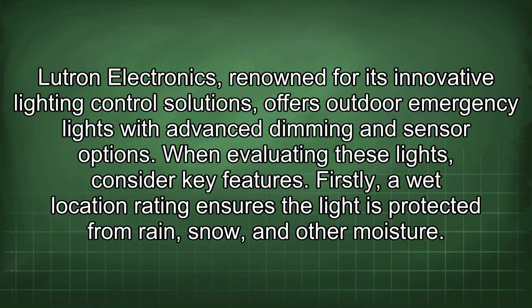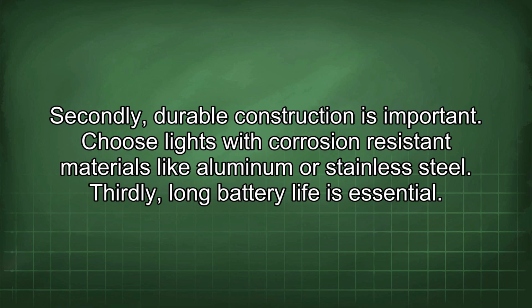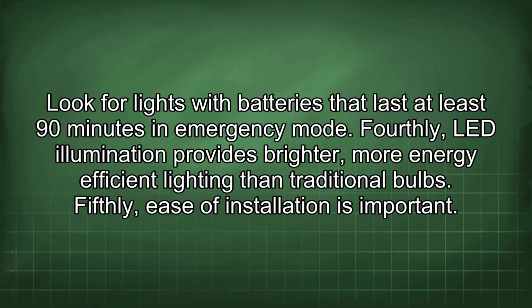Firstly, a wet location rating ensures the light is protected from rain, snow, and other moisture. Secondly, durable construction is important. Choose lights with corrosion-resistant materials like aluminum or stainless steel. Thirdly, long battery life is essential. Look for lights with batteries that last at least 90 minutes in emergency mode.